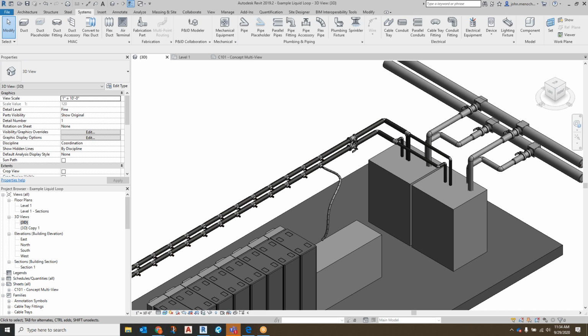I'm wondering if there's value in starting out thinking about how much power I provision for that area on the floor, where I'm going to support some liquid cooling. Then, maybe arbitrarily or as a guess, what percentage of that provisioned power do I think could end up liquid cooled? So if I've got a cluster of racks where I'm going to put some liquid cooled racks, maybe some tubs, and I've got a megawatt there, I say okay, maybe I'll provision for 80%, or 800 kilowatts. Maybe a crude way to look at it, but a simple way to get the conversation started.